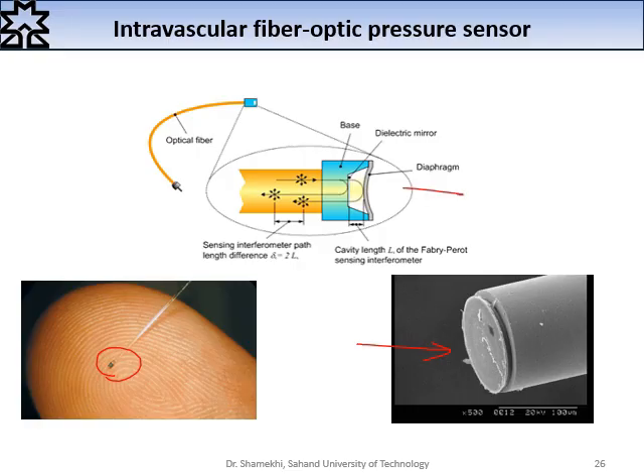Some other types of measuring can also be used. For example, phase shifting can be used as the main index to detect the deflection of the diaphragm. If we send light with a specific phase, the deflection can change the received light at the detector side. Therefore, the phase shifting between these two lights can be measured for calculating the pressure, and we can calibrate the deflection, the phase, and the applied pressure.